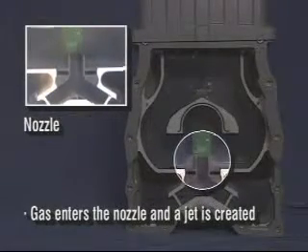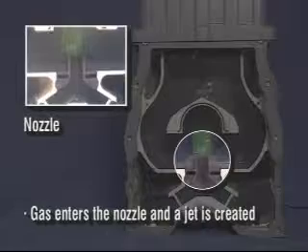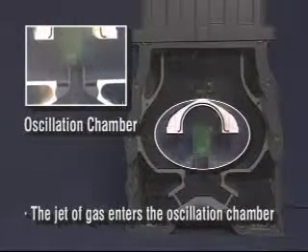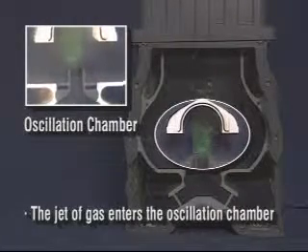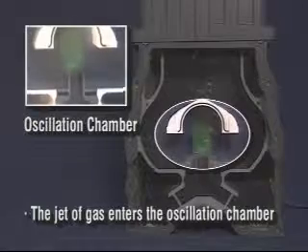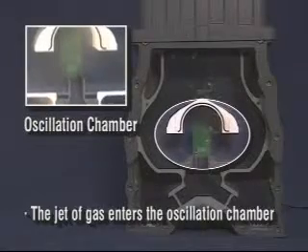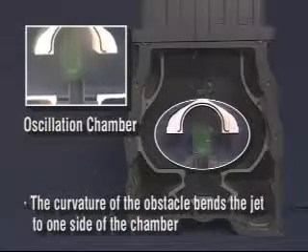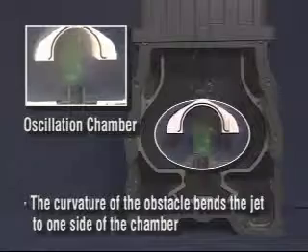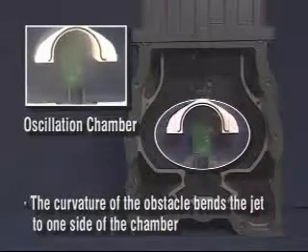Gas enters the nozzle and a jet is created. The jet of gas enters the oscillation chamber where the obstacle controls the fluid feedback paths. Due to the curvature of the obstacle, the jet is bent to one side of the oscillation chamber.